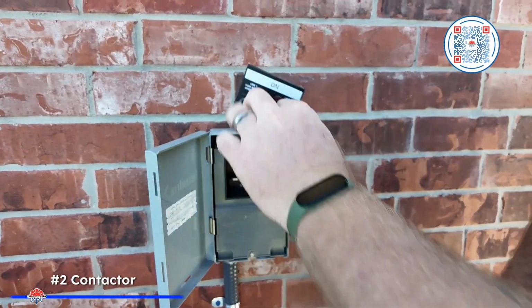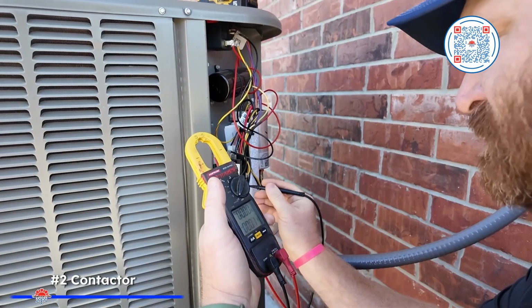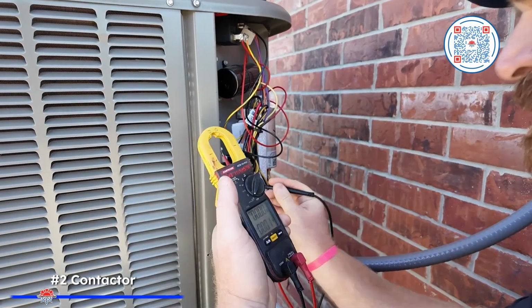The number 2 most recommended repair that we do during spring maintenance is the contactor. The contactor is basically a switch that transfers power from the incoming side to the outgoing side to the components of the system. If that fails, your system is down. There's no ifs, ands, or buts about it. Your system is down if that contactor fails.